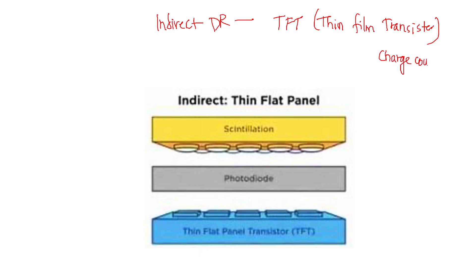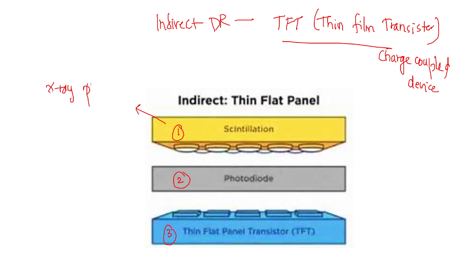The thin film transistor system consists of three layers. The first layer is a scintillation layer, the second layer is a photo diode, and the third layer is a thin flat panel transistor. The scintillation layer mainly converts x-ray photons to light. For this conversion, the scintillator layer uses cesium iodide.